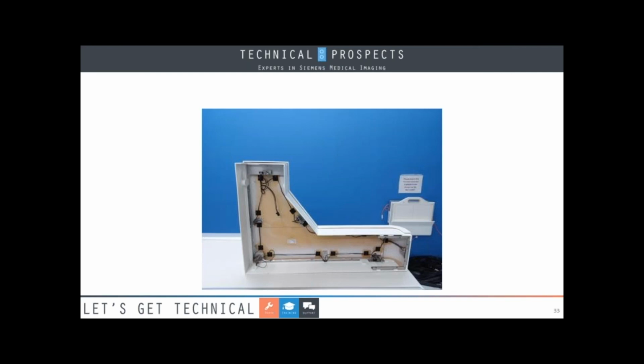But one nice thing that Siemens did was they provided a jumper. You can see where that plug is right there. Instead, you can put a jumper on the machine and jumper it out, so you can isolate the issue. If it takes the error away, your problem's with this switch bank. If it doesn't, you can pretty well say that's not your issue.